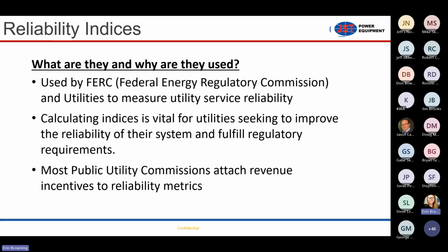If there's a fault event like a tree branch hitting a line, that recloser is going to go through a cycle of trip, close, trip, close, trip, close to try to clear that fault. A lot of times the opening and closing of the recloser on the line is physical enough that it knocks the tree branch free by the third close attempt. Then, once the tree branch is gone, the recloser closes again and there's no fault present, so it stays closed. That's the idea of the recloser: to give the line an opportunity to resolve the fault condition without going into an immediate lockout situation. Because once you go into a lockout situation, your customers don't have power anymore.